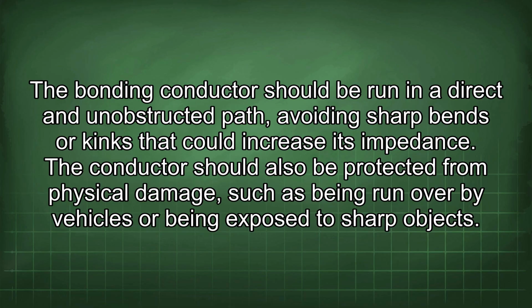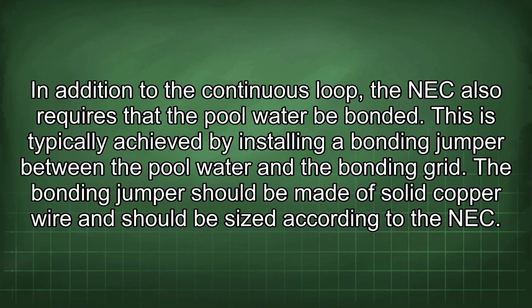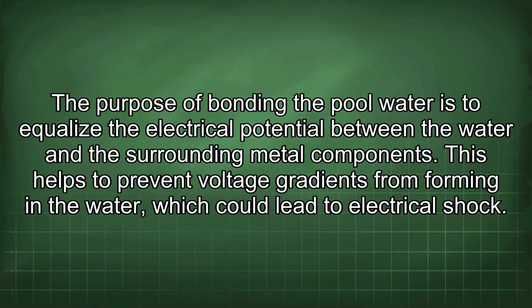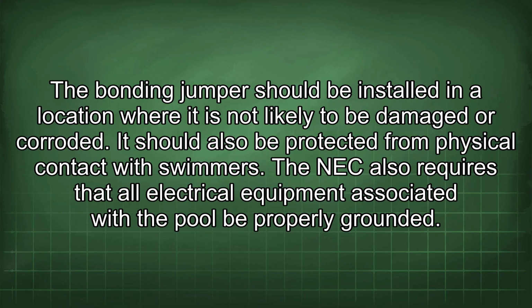In addition to the continuous loop, the NEC also requires that the pool water be bonded. This is typically achieved by installing a bonding jumper between the pool water and the bonding grid. The bonding jumper should be made of solid copper wire and should be sized according to the NEC. The purpose of bonding the pool water is to equalize the electrical potential between the water and the surrounding metal components. This helps to prevent voltage gradients from forming in the water, which could lead to electrical shock. The bonding jumper should be installed in a location where it is not likely to be damaged or corroded. It should also be protected from physical contact with swimmers.